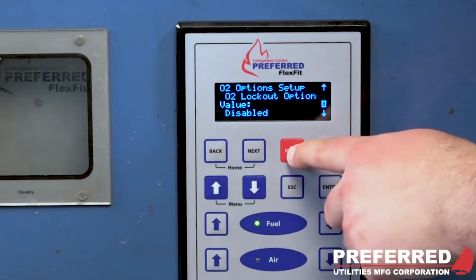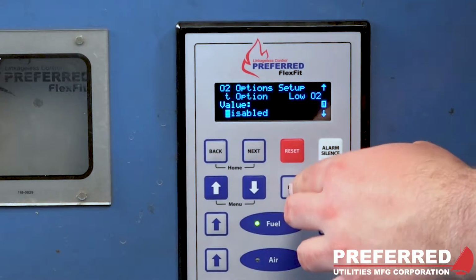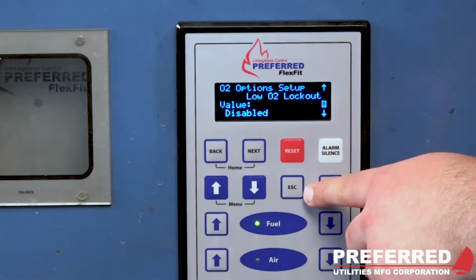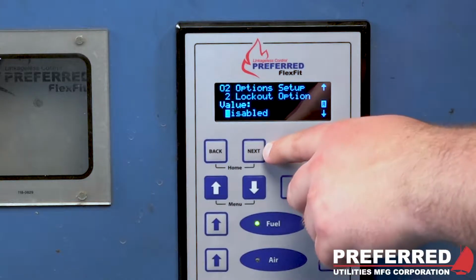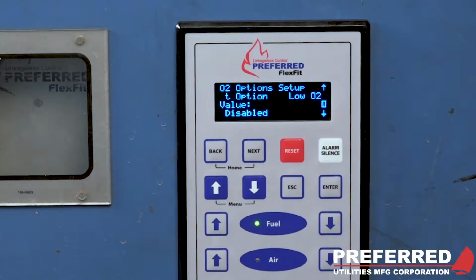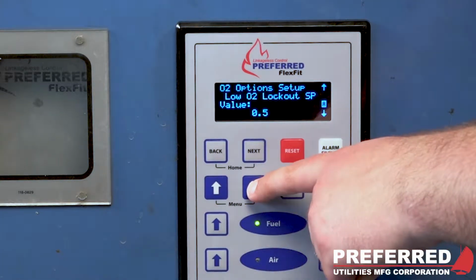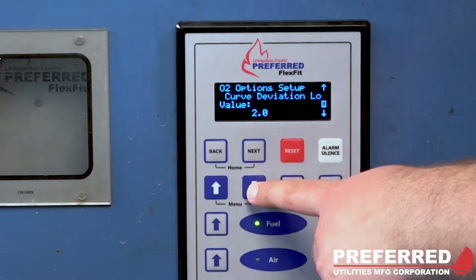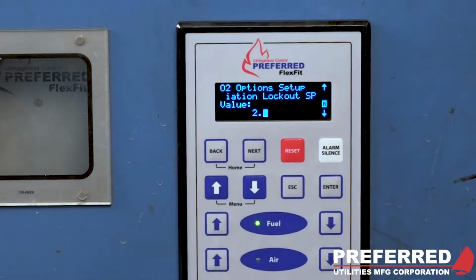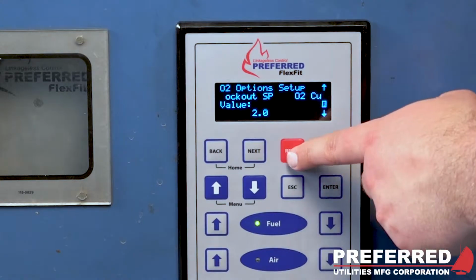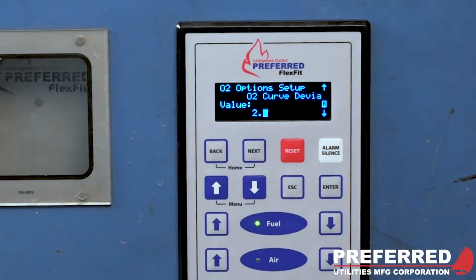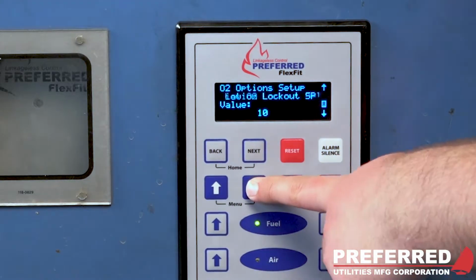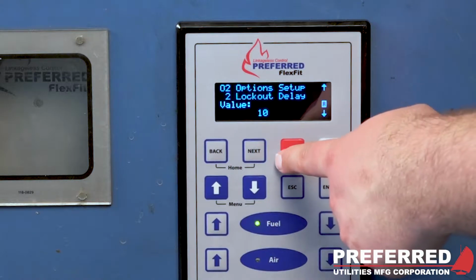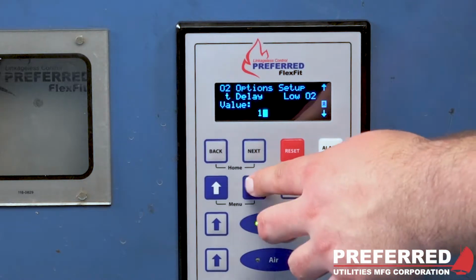And we just got an alarm, so that's fine. Silence that. If you want to enable your low oxygen lockout, you can do that here. And then put a set point for that lockout. Below that, if you would like to have a lockout for O2 set point deviation, you can also add that, and that would be if your actual O2 deviates from the curved set point, you would get a lockout. And also there's a time delay for any O2 lockouts that you can add in.